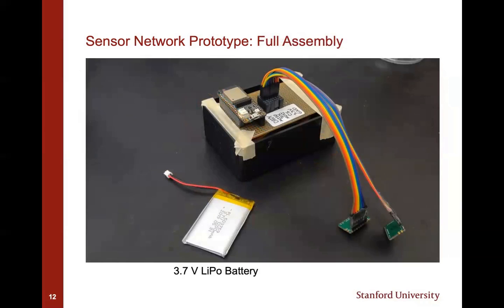So here's a look at the fully assembled prototype. The SAM32 microcontroller is mounted and connected in this picture to 2 sensors. I would like to point out that the wiring used here is very basic and indicative of this prototype's proof of concept role. In a real transformer, these wires would have to be much tougher and able to withstand high temperatures and submersion in hot mineral oil for decades. The sensor network is powered by a 3.7 volt LiPo battery and can run up to 6 sensors at once.